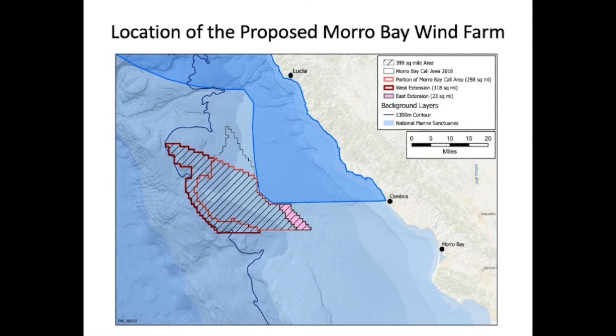What about the capacity of this wind farm? There's enough room for 350 to 400 turbines, so I split the difference and said about 375 wind turbines, spaced about a mile apart, each with a nameplate capacity of 14 megawatts - that maximum power generating up to about 120 amps of 60 cycle 3-phase AC electricity at 66 kilovolts. Now 14 megawatts is actually pretty conservative; there will be 14 megawatt turbines on the market within a year or two, and by the end of this decade when this is deployed there could be 16, 18, maybe even 20 megawatt turbines. But I'm going with a conservative number of 14 megawatts.